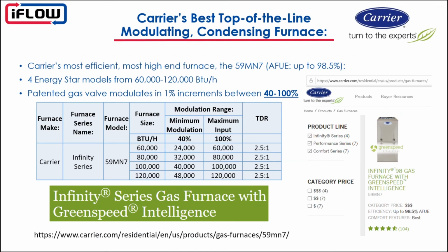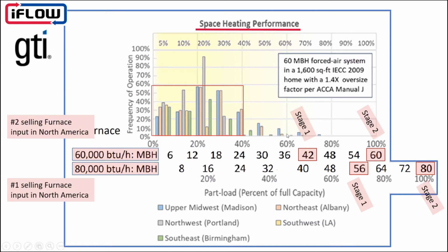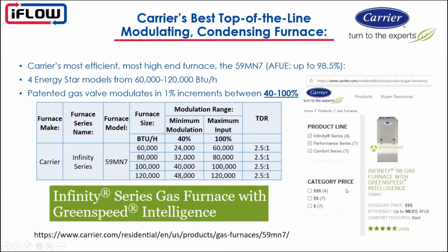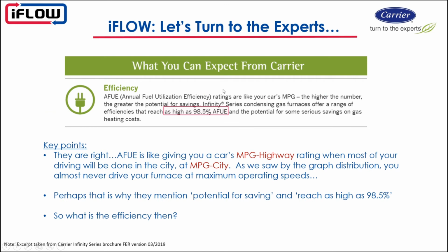Most of the operation is not in this higher end, which we would call highway speed, let's say. It's mostly in this lower end, so we would call this MPG city, if you will, and then MPG highway at this end as we get closer to 90 or 100% capacity. So perhaps that's why they mentioned that the AFUE gives you the potential for savings. It doesn't guarantee you those savings, it's the potential for savings.